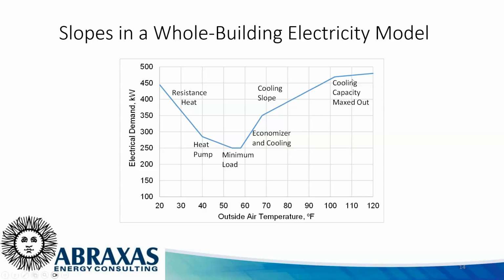So we'll have a temperature, say the typical office building will have a minimum load at some temperature, typically in the mid 50s. Above that, if we have an economizer, you'll have a fairly steep slope as cooling is required more and more, mechanical cooling. And then once the economizer is no longer operating and the damper is at minimum position, you'll have a slightly lower cooling slope. And if you run out of cooling capacity, the slope will go to near zero over on the far right. Things will try and run harder, but they really can't put out any more cooling, and so it gets near flat.